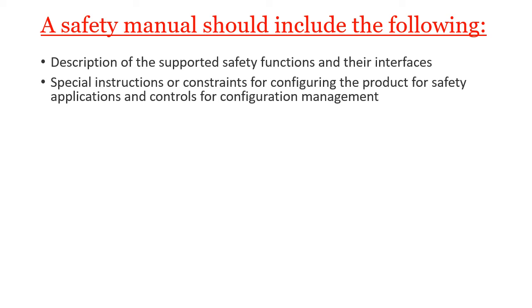There is a dip switch that needs to be enabled or disabled for this write protection. If you do not do the write protection, the safety action gets void. This is just one example that some special instruction or configuration needs to be followed.